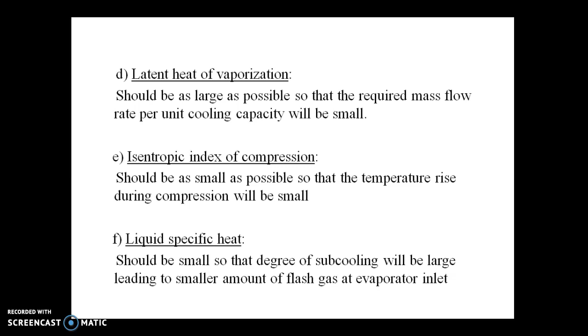The next one is the liquid specific heat. It should be small so that the degree of subcooling will be large, leading to smaller amount of flash gas at evaporator inlet. Vapor specific heat of refrigerant. This value should be large so that the degree of superheating will be small.